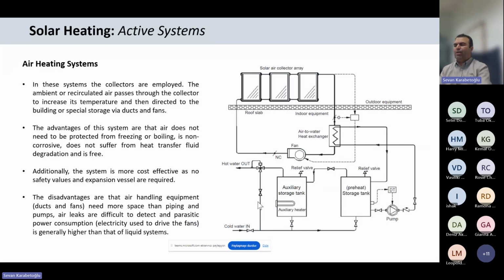In this case, if you want to warm up a space with air, we use air heating systems. Therefore, circulation will be supplied by a fan instead of a pump, of course, so the electrical loads are less than with the water pump. The main advantage of the system is that air does not need to be protected from freezing or boiling. These thermophysical phase changes do not occur in this case, and it is non-corrosive also. We don't suffer any heat transfer fluid degradation. Additionally, it is cost effective because, as I said, electricity consumption is less.